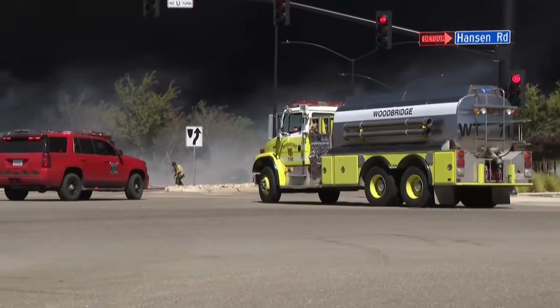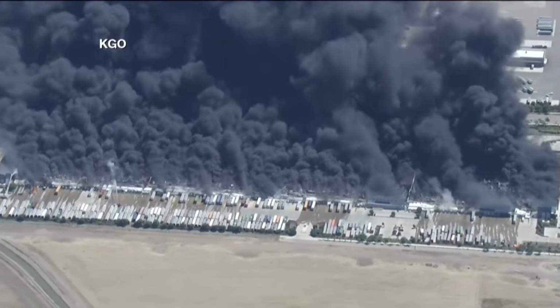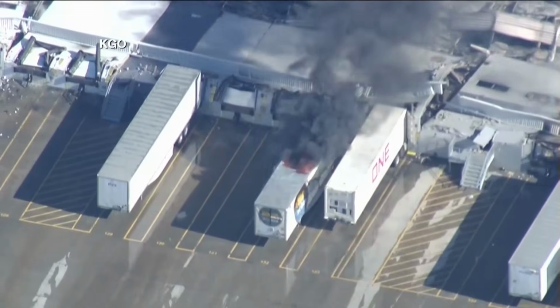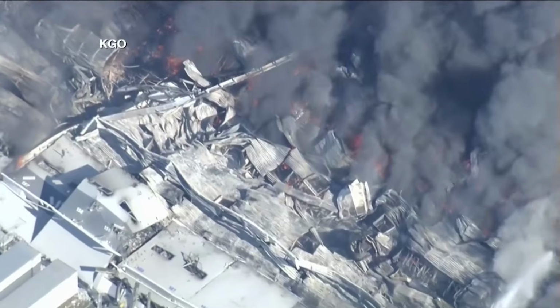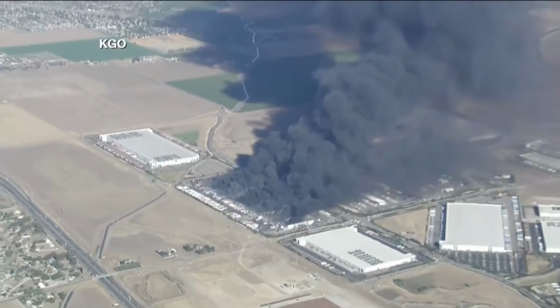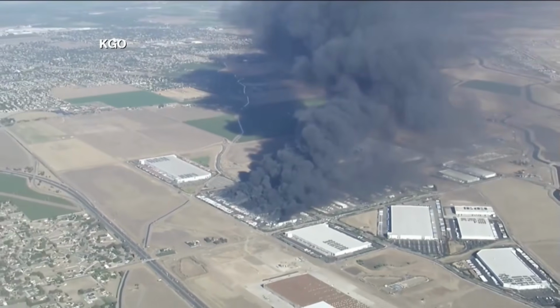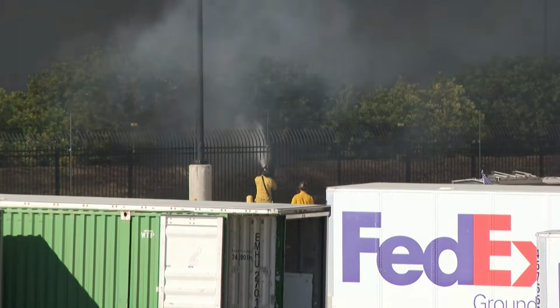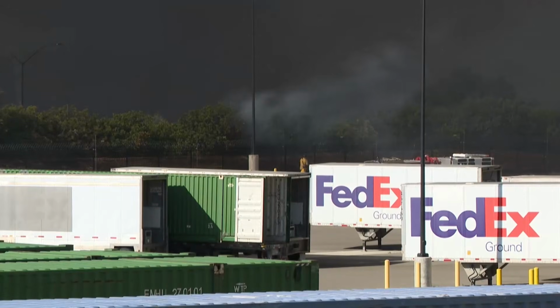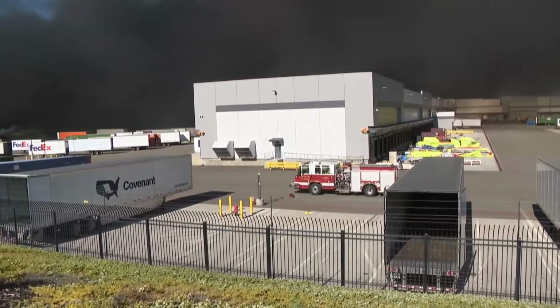Rule of thumb, it's about 1 year per business, especially for these larger warehouses. He says state code requires most warehouses to have their fire suppression system tested once a year. That involves ensuring the sprinkler heads and valves are operational. That's typically done by a third-party private company. And every 5 years, a facility is required to have a deeper internal pipe inspection to ensure the water flow is not obstructed.